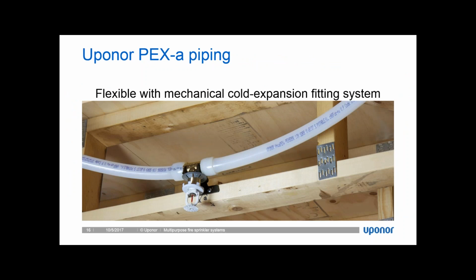So when I'm installing PEX tubing above a structure, what happens is when I go over the top of the bottom chord of truss, or when I drill through a joist, I have to drop down to the ceiling level. Well, the pipe is flexible enough that we can just do that using the flexibility of the tubing. So I don't need to cut a drop in for that sprinkler. That eliminates an additional fitting at a higher level to get down to where that sprinkler needs to be. And then when I need to go up to a new hole that I've drilled to get through the structure, I just use the flexibility of the tubing to get back up there.